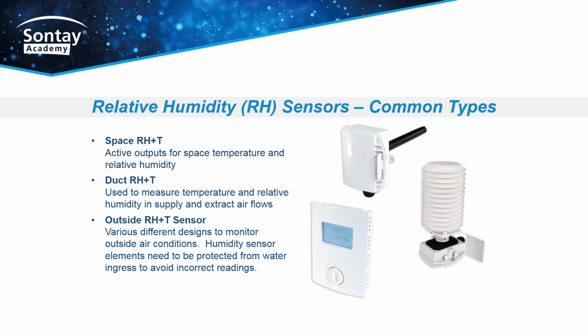Measuring relative humidity is commonplace in ducts and conditioned spaces. Some applications require measurement of outside relative humidity, and thus some means of protecting the sensor from water ingress is important. On large-scale systems, this is often achieved by using an aspirated chamber, fully protected from the elements, but another common method is to protect the sensor element itself by using a rain shield.